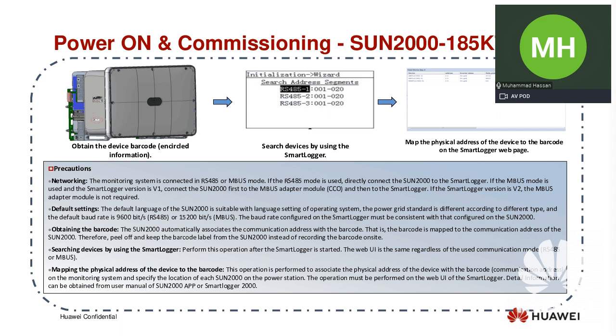If you use the SUN2000 app, you will only be communicating with a single inverter. The screenshot mentioned here is from the smart logger. I've taken it from the smart logger. As you can see on the right side, these are the inverters which are communicating with the smart logger after the commissioning of the site.